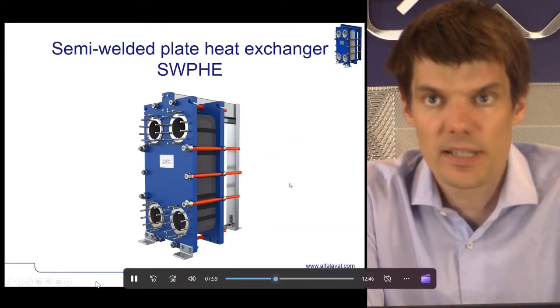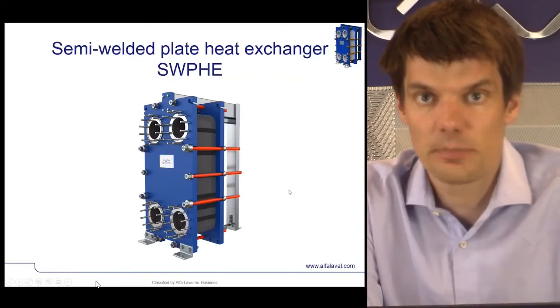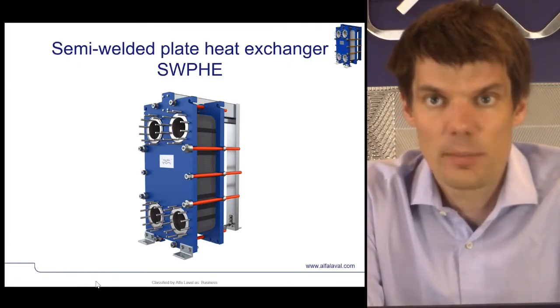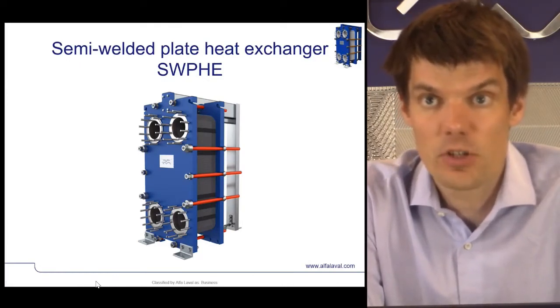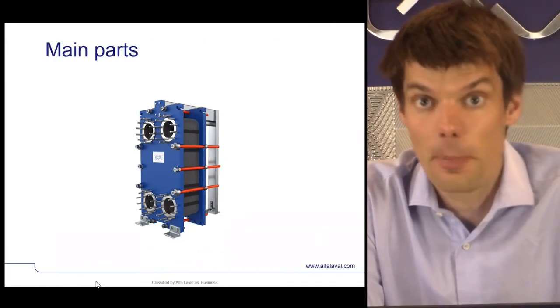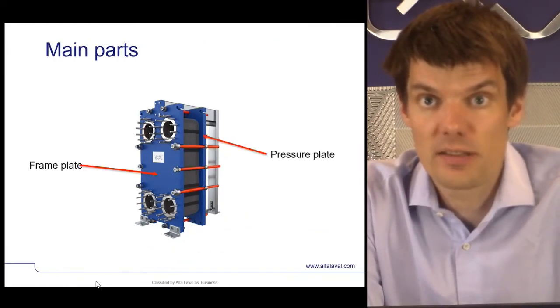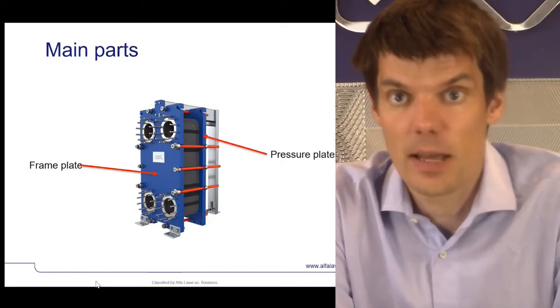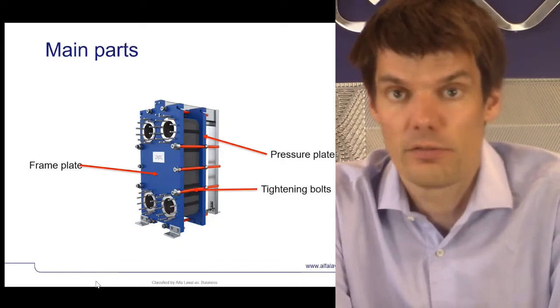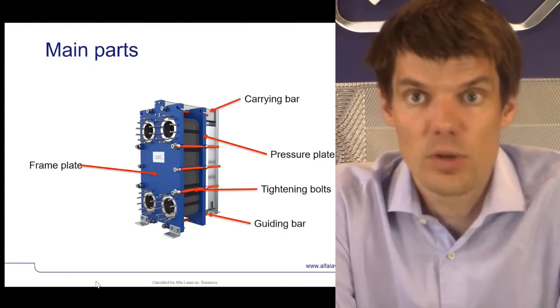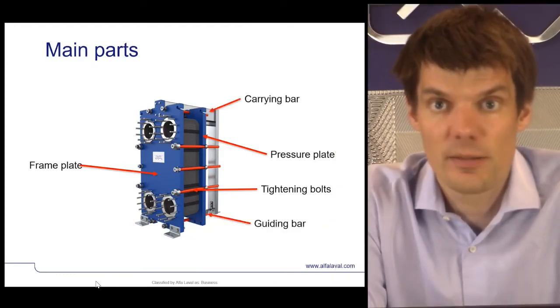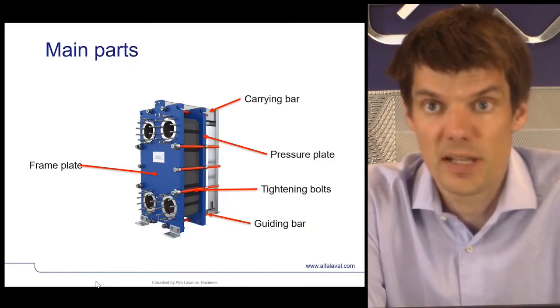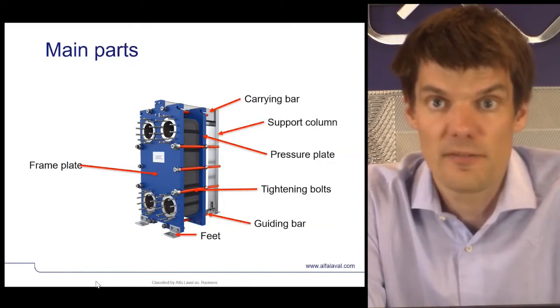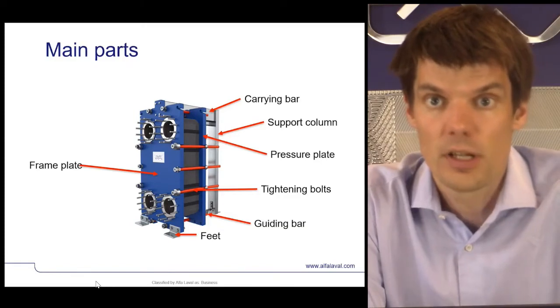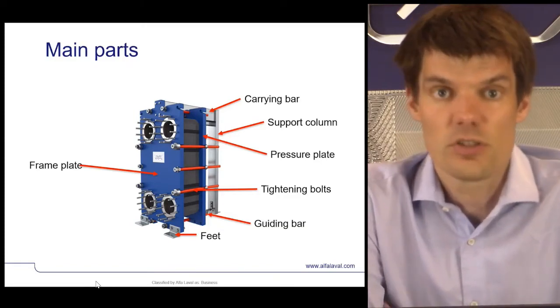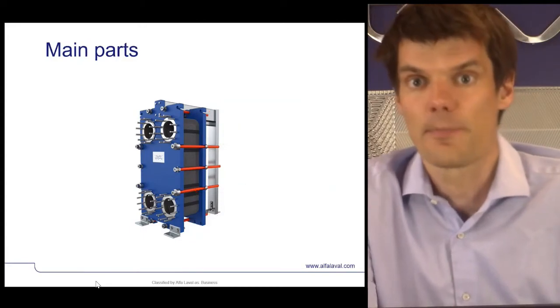And with that said, let's have a closer look at the semi-welded plate heat exchanger. A semi-welded plate heat exchanger is made up of the same concept as a plate and frame heat exchanger. There are a frame and a pressure plate, which together with the tightening bolts make up the pressure vessel and form the main unit. There will be a carrying bar and a guiding bar, which help to keep the plate pack straight. And there will be feet and a support column, which make sure that the structure stays where it's supposed to be and does not go anywhere else.